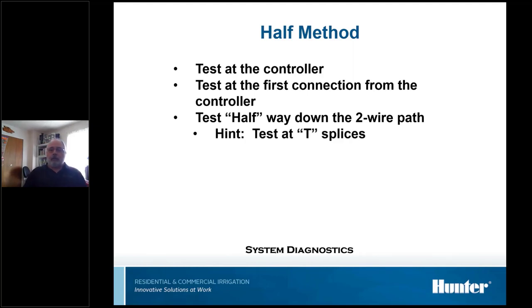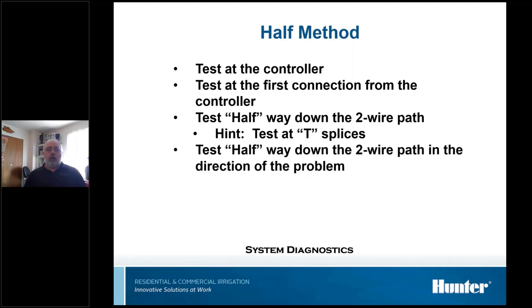Oh yeah, if there's T splices, if you got splices out there, they're logical places to test. Because then you can disconnect three wire paths at once. So you can figure out which one of the outgoing paths has the problem on it. Just try to be as logical as you can about how you go about doing this. Then we're just going to disconnect and see what happens. We disconnected a point and the controller now starts working. I know my problem's further out. If I disconnect and the controller's still screwing up, I know my problem's between there and the controller. So you're just going to keep disconnecting until you find your problem.